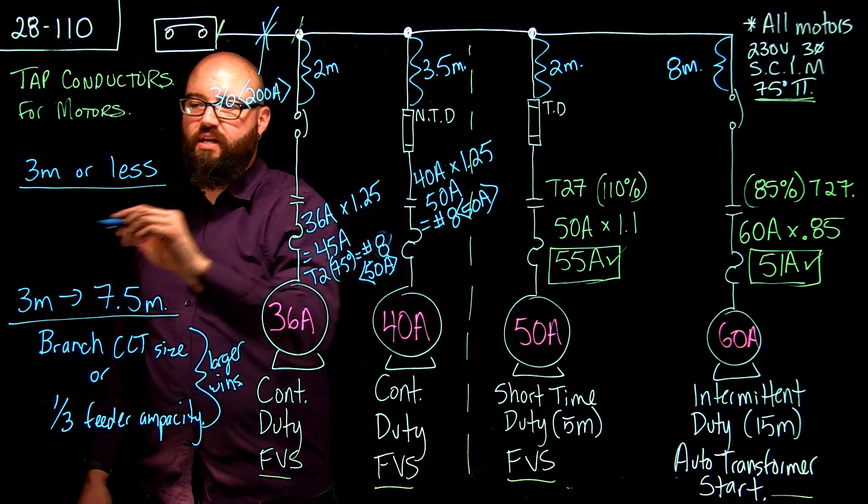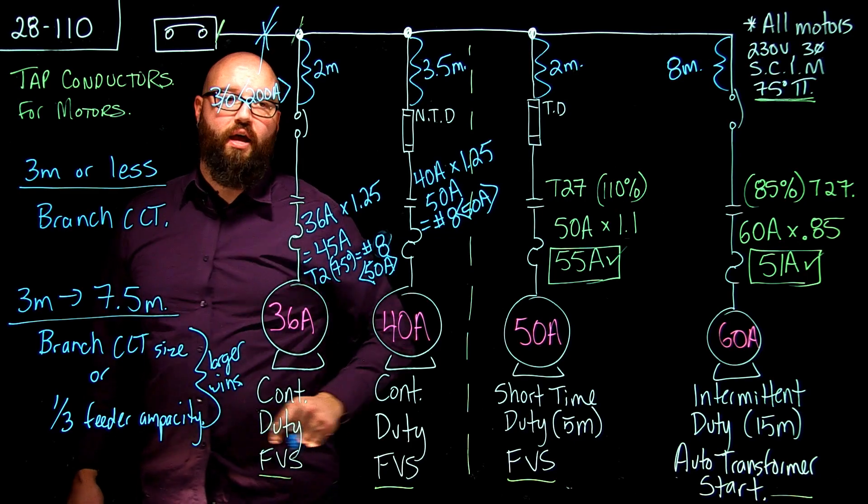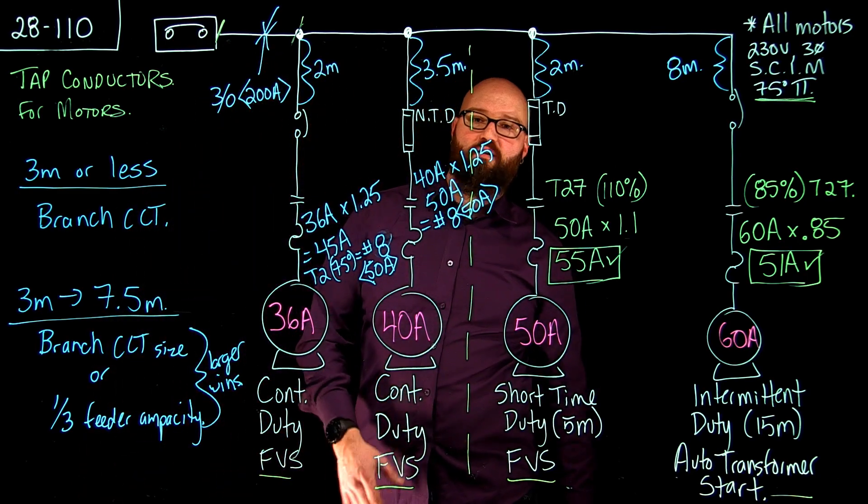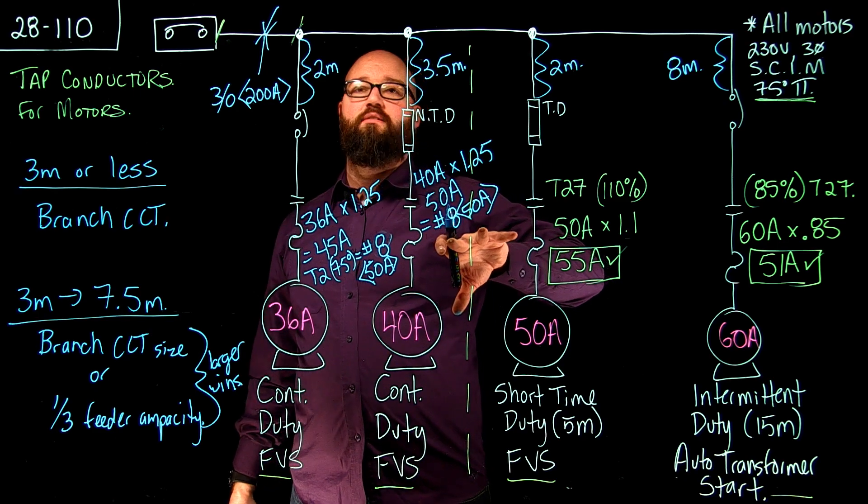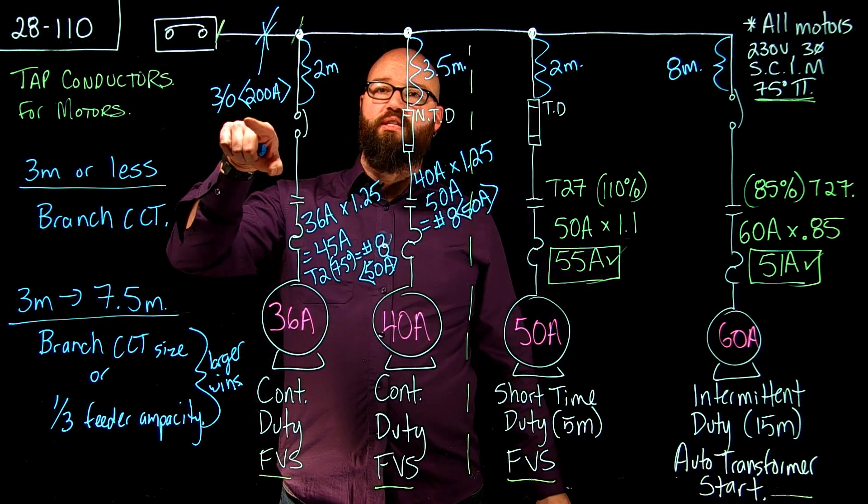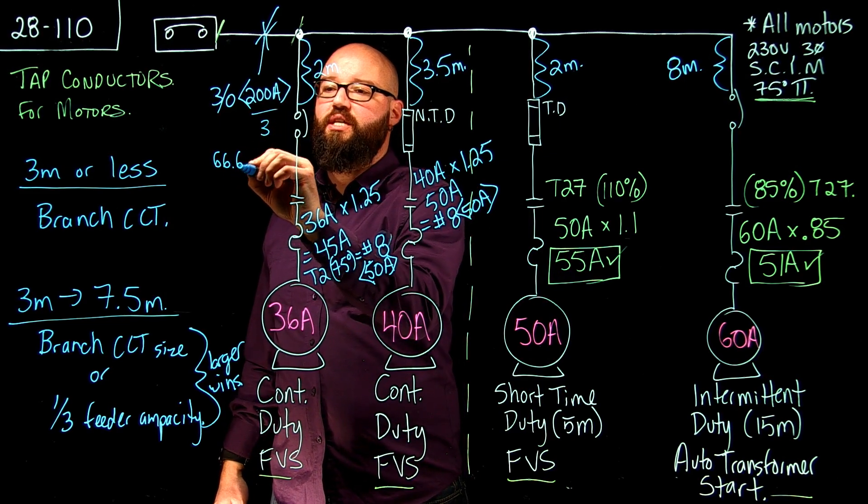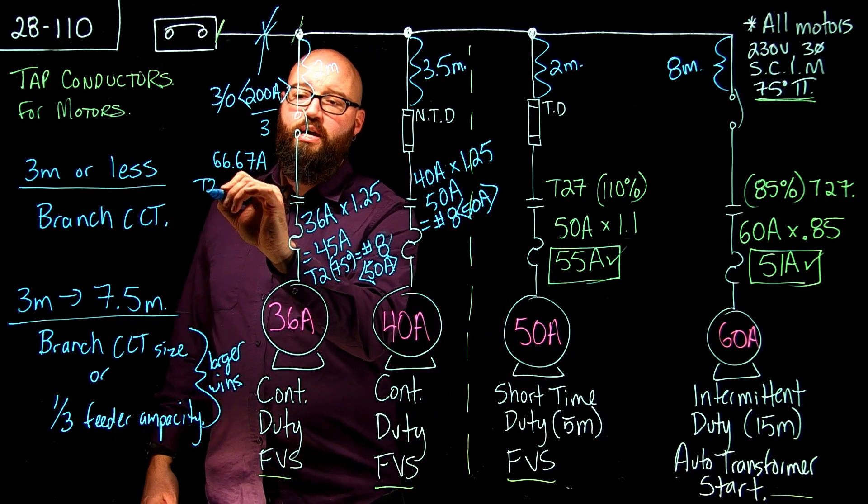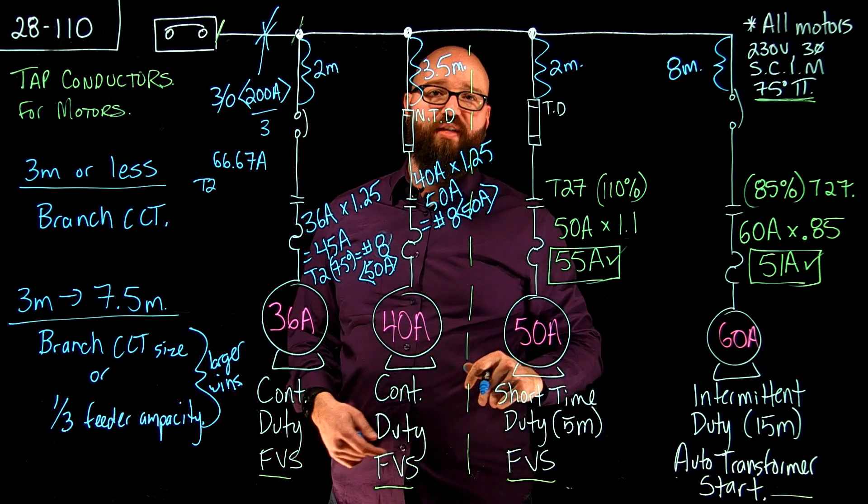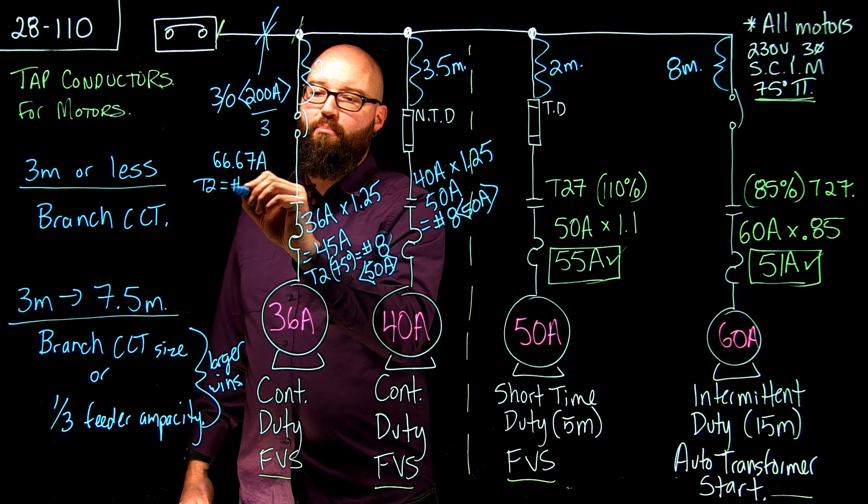it becomes the minimum ampacity for this tap conductor. 3 meters or less what we did here really it's just whatever your branch circuit is. That'll suffice as a tap conductor. So we have a choice now between a number 8 or one-third this feeder ampacity. So we're going to take that divided by 3 gives us 66.67 amps which if I was to go to table 2 and size a conductor based off of that one-third ampacity I would select a number 4.